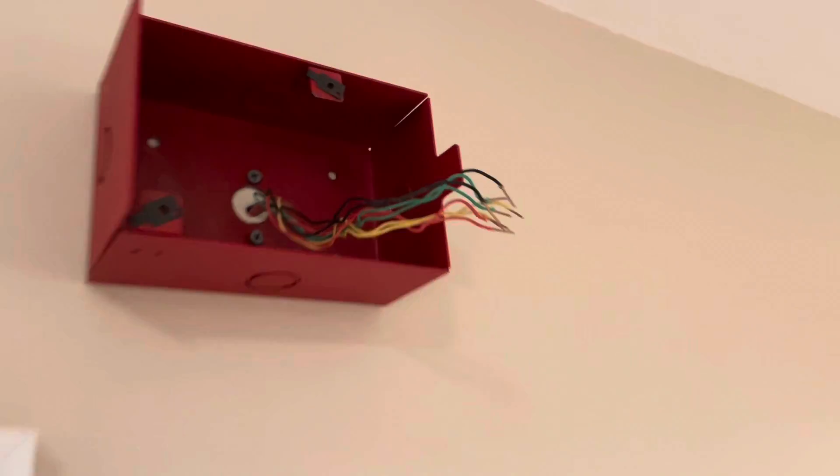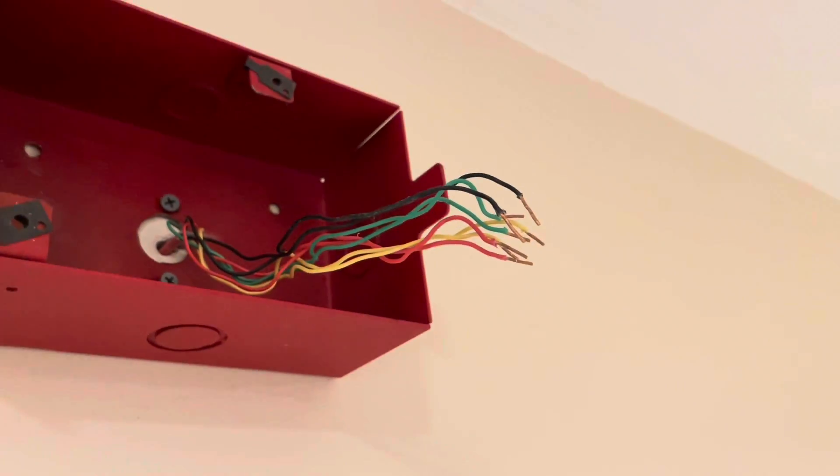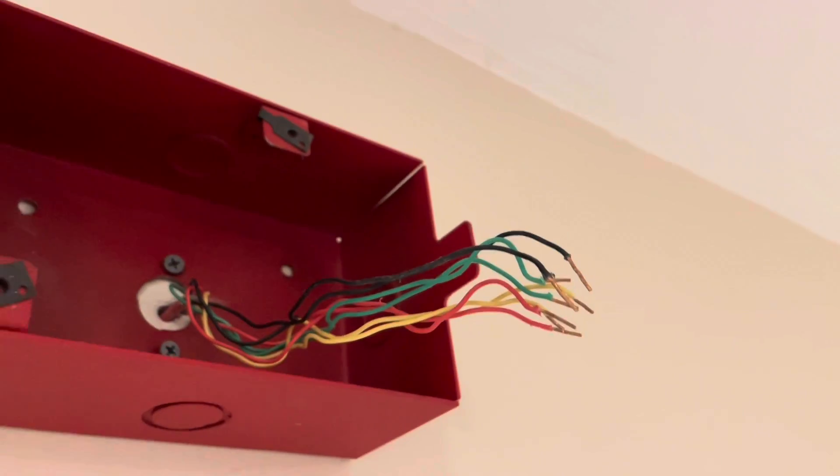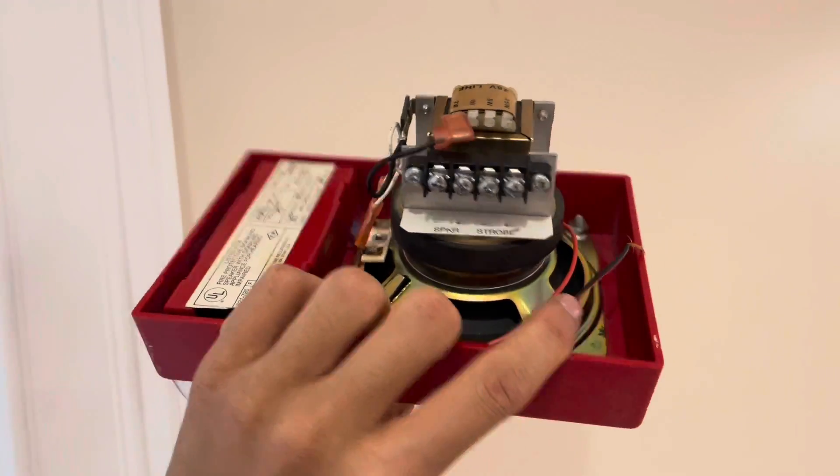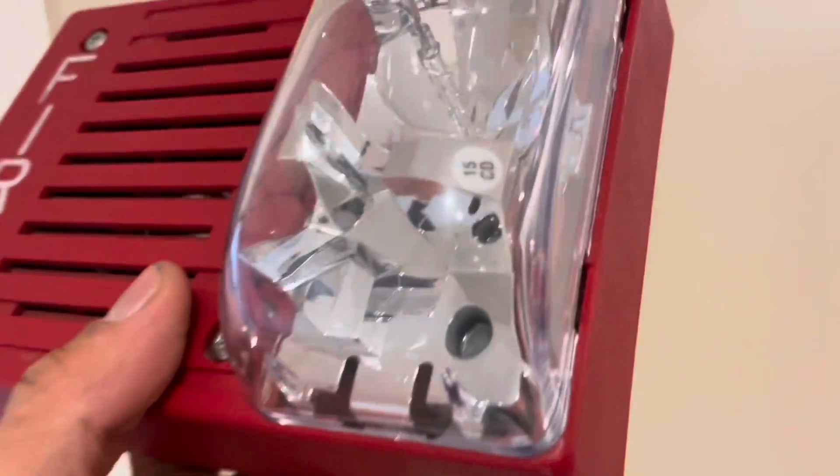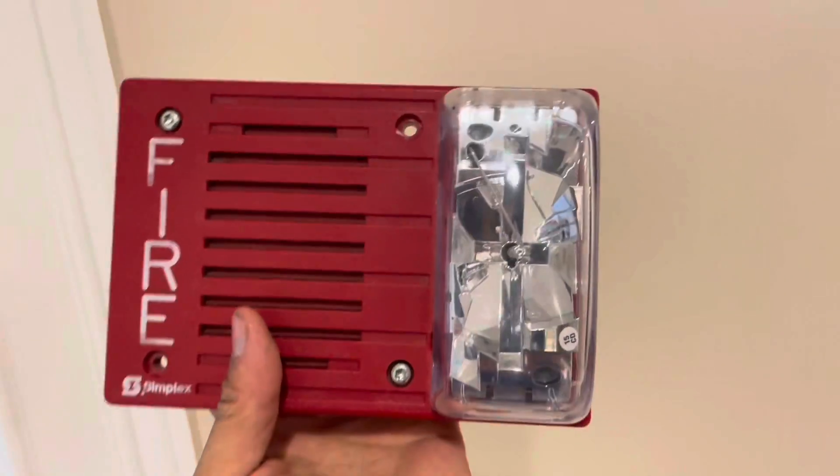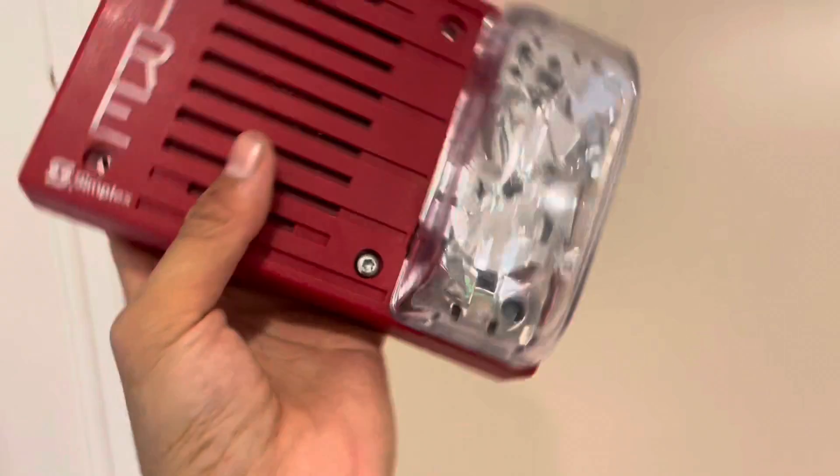So the wiring for these is really simple. You see I have two pairs of wires. Black and red go to the strobe output and the yellow and green wires go to the audible output. Now in this case I actually had to modify this device. The strobe on this is a syncable strobe. All the devices I'm putting up today are syncable so they're all going to sync.